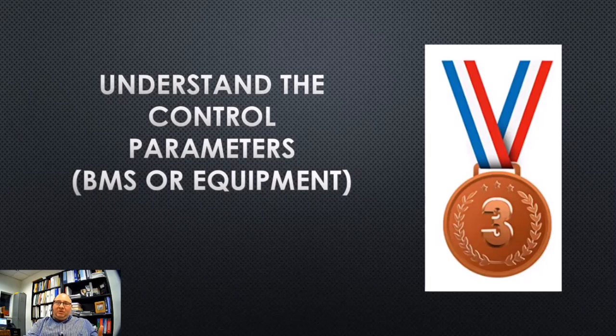Then once we know the motor and the drive parameters, we have to know how it is being controlled. Is it going to be initiated from a BMS, with a start/stop command and speed reference, or is it going to be based on the equipment? For example, you might see VFD drives on a Carrier unit, where Carrier's MBB board, the board located near the economizer section, controls the operation of the VFD drive. It is done internally within the unit. Same thing with an AAON. They will control the VFD drive with their own internal software and control logic. Whereas if we're adding this to a site, we may be controlling it through a BMS, through an external means of operation.